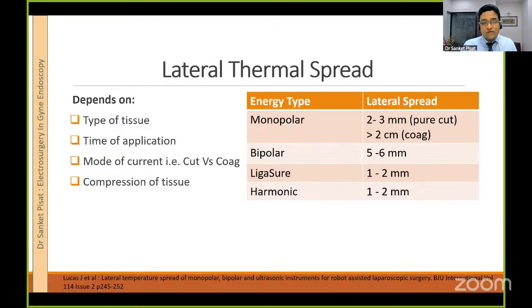The time of application to tissue matters: quick in, quick out, the same type of energy applied will have less lateral spread if the time of application is less. Then there is the mode of current, cut versus coagulation. People ask whether monopolar has less lateral spread or bipolar has less lateral spread. But in a sense, the question is wrong, because you are not stating whether you are talking about monopolar cut versus monopolar coagulation. And the last effect is compression on tissue. The more you compress the tissue, the easier it is for current to flow from one blade to another, particularly in bipolar. And so, the more the compression on tissue, the less is the lateral spread.